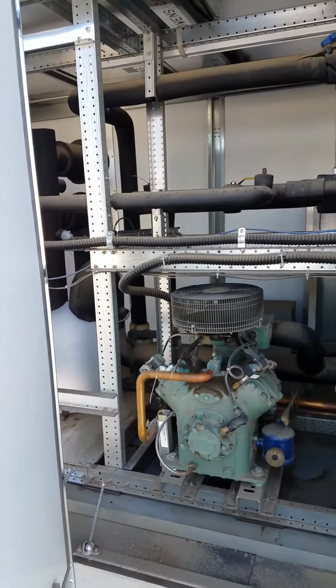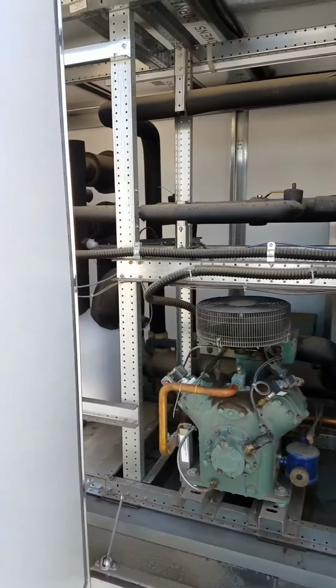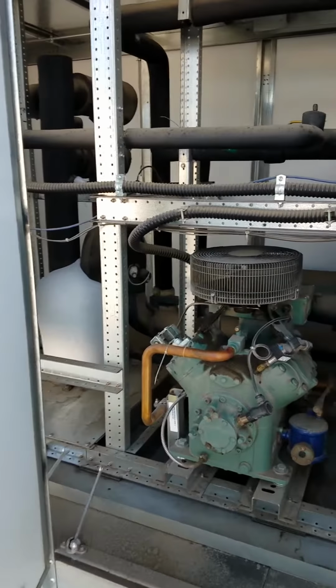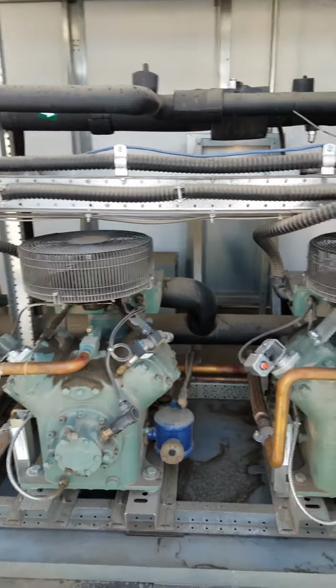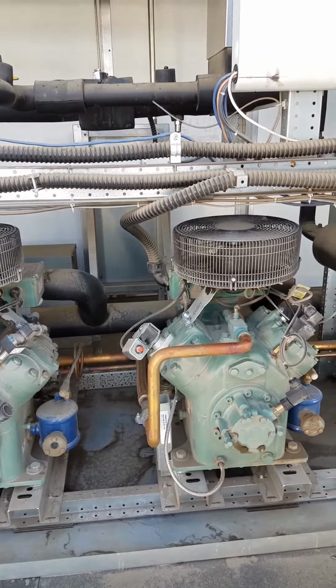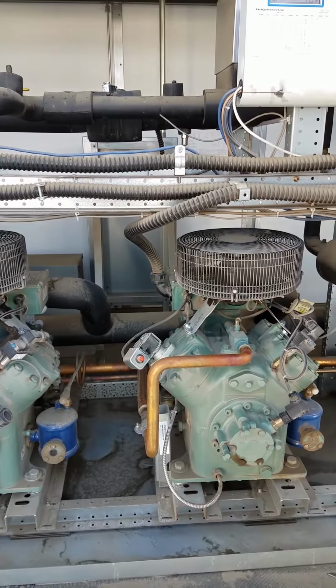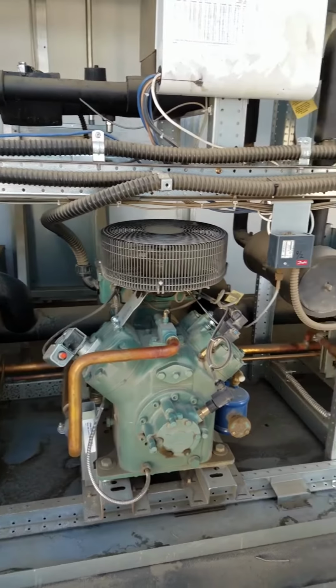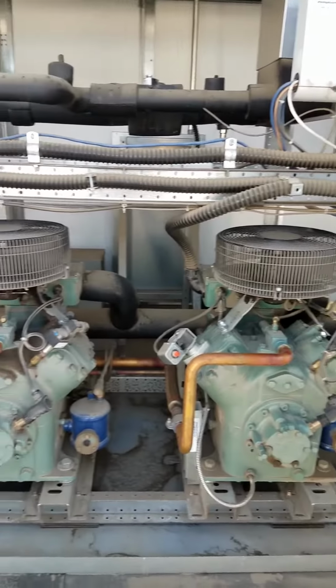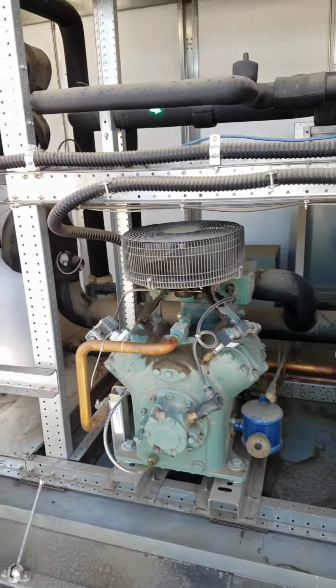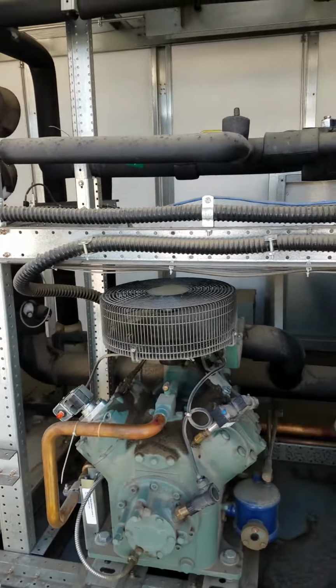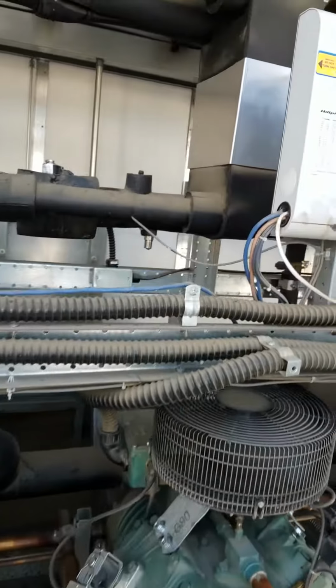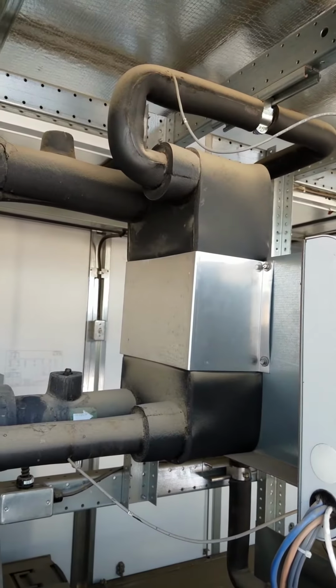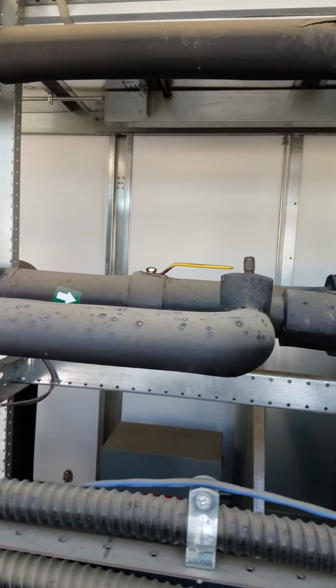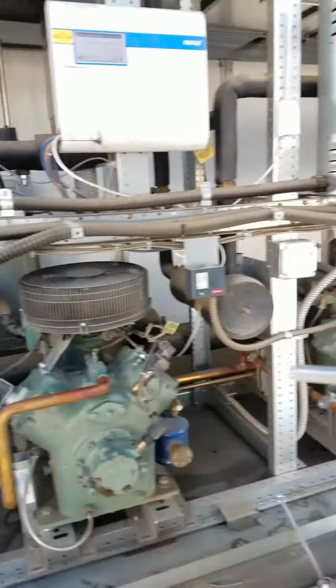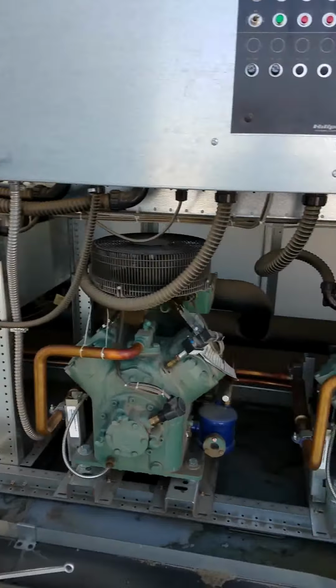Then over here, I open up all the doors to the rack. And you got your refrigeration compressors. These are pumping refrigerant. In this case it's 407A, I believe. I haven't checked the label, but I'm almost positive. Yeah, 407A. These are all on the common discharge, common liquid line, common suction. They're all tied in. So it looks like there's only 4 compressors.